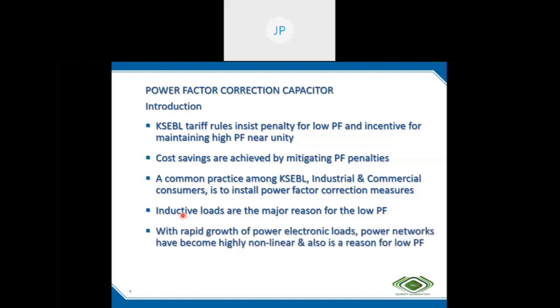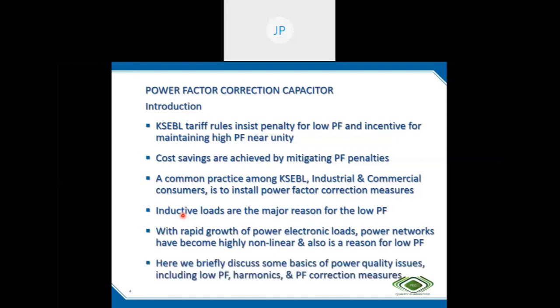Another reason is power electronic devices. Power electronic devices or equipment based on power electronics are widely used to save energy, to reduce losses, but they are nonlinear loads. They draw distorted current, and distorted current produces harmonics. The current harmonics produce voltage harmonics also, and both produce low power factor. The existing power factor is further reduced because of the power electronics devices.